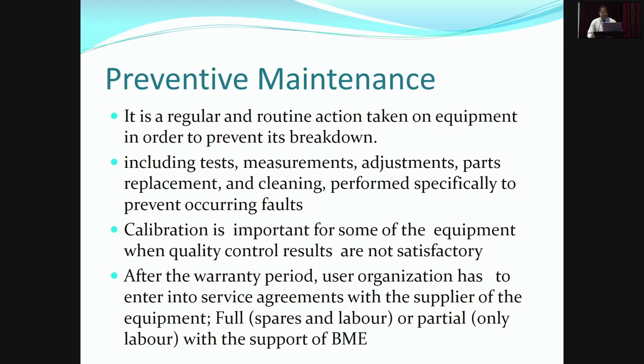Calibration is one of the important preventive maintenance measures for some equipment, used when quality control tests are not satisfactory. For example, in a laboratory, you start the day with quality controls, but if these are not satisfactory, then you have to calibrate these analyzers.